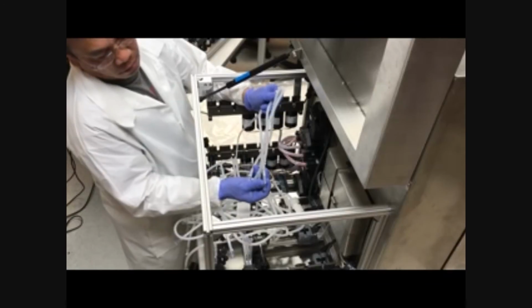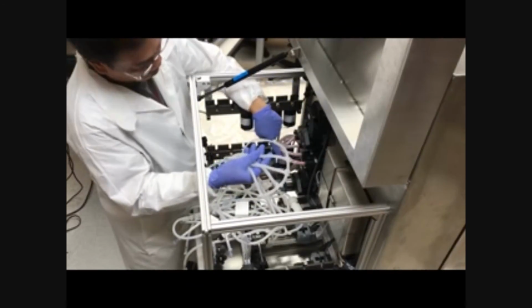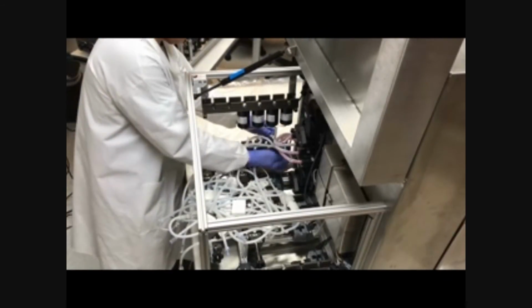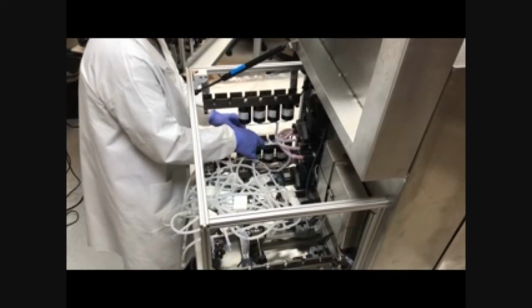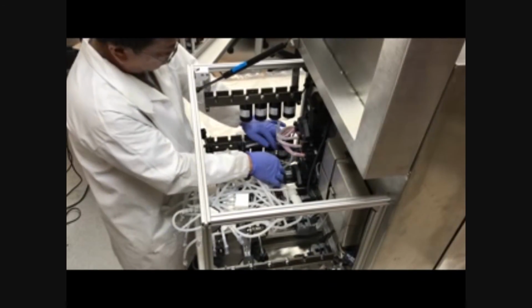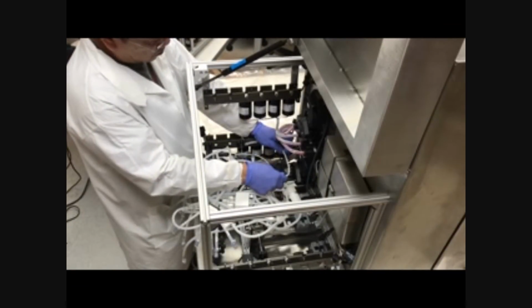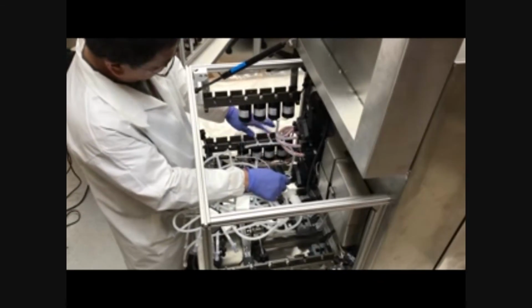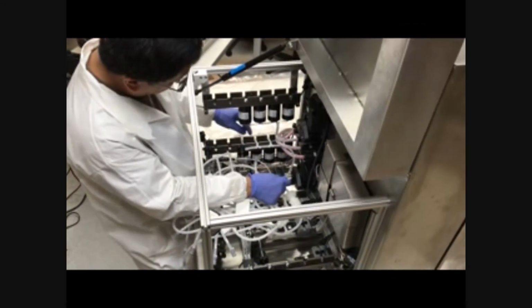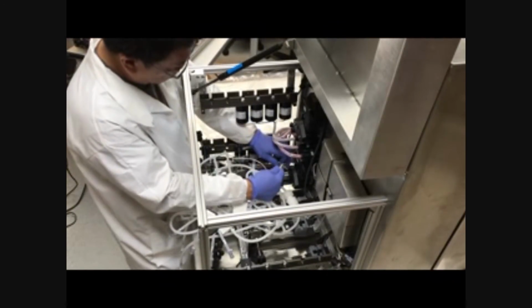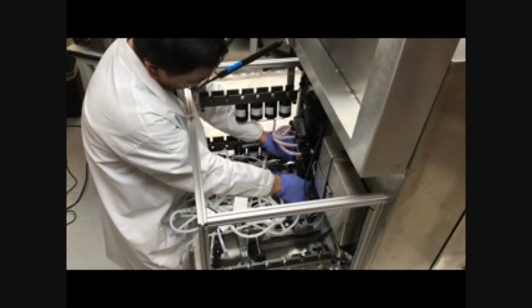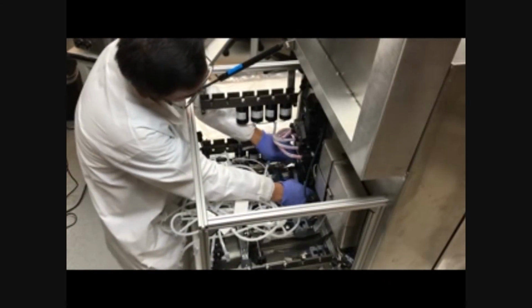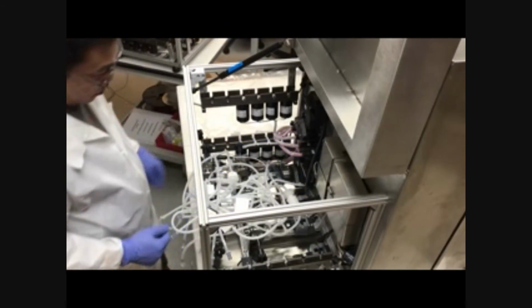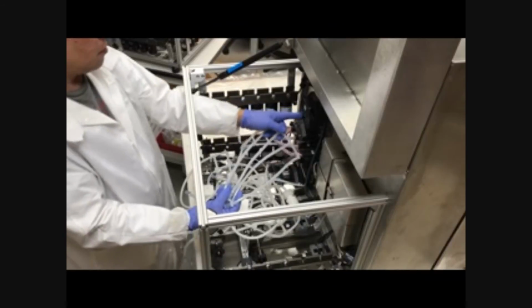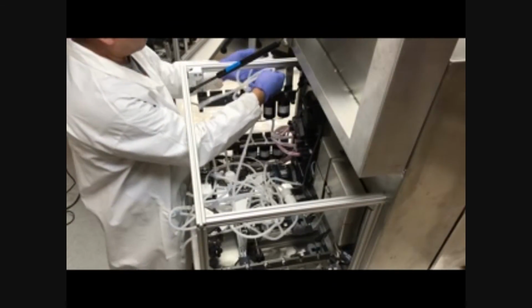He's got the 4 inlets for pump A that he's setting through each of the channels on the pump A manifold. Okay, so the solenoids are at the bottom, and they have a pinch clamp that moves up, the plunger moves up, and it will pinch the tubing. Alright, so he set that, and now he's taking the pump tubing through the peristaltic pump, threading it through the peristaltic pump, and there the pump tubing is installed. And he's going to do exactly the same thing with the B pump and the B valves. Okay, so there he goes.